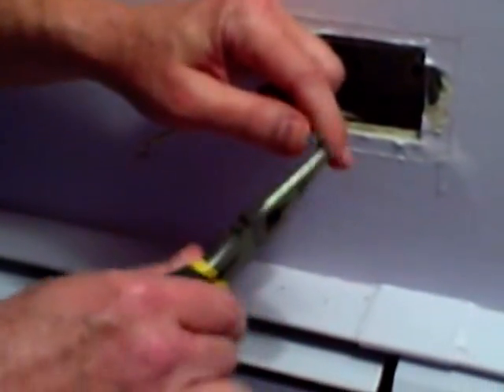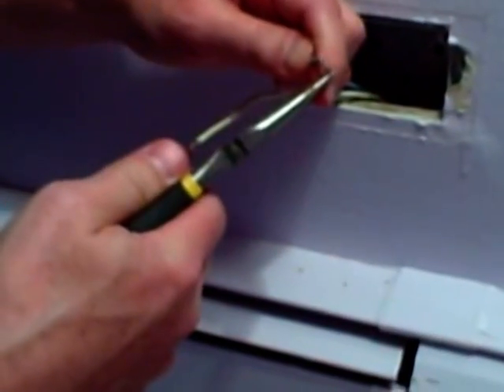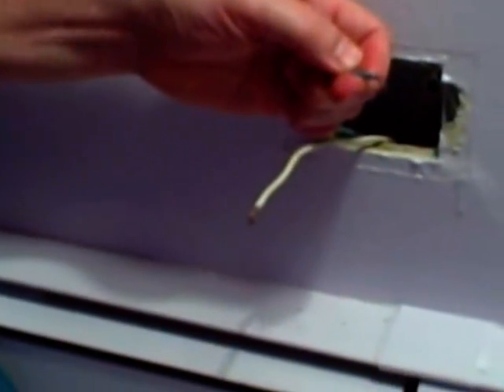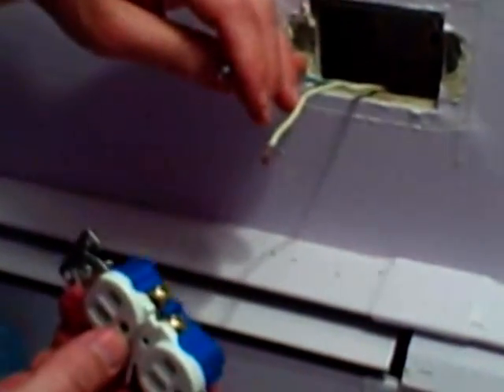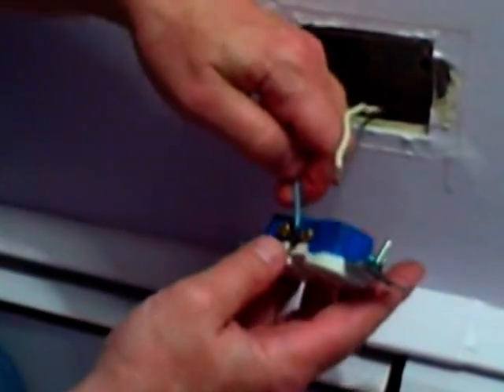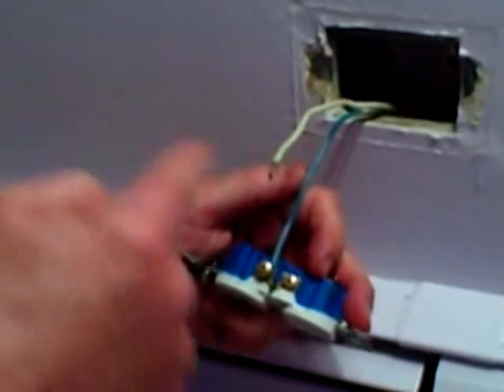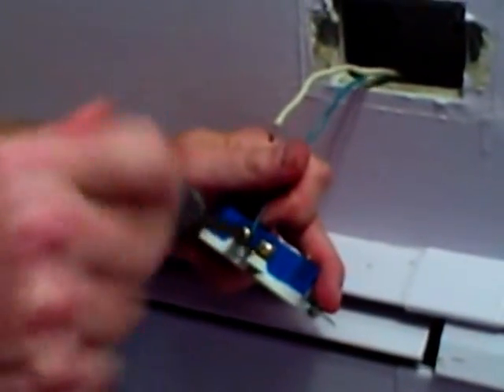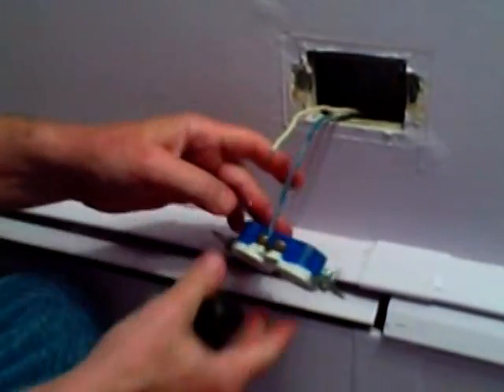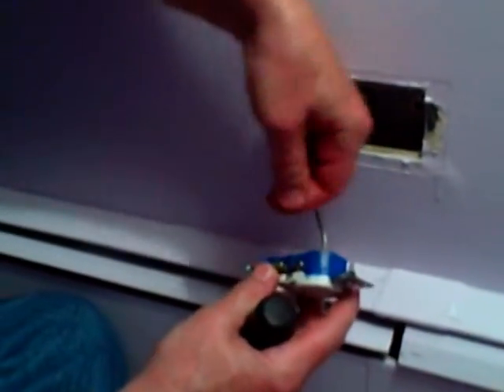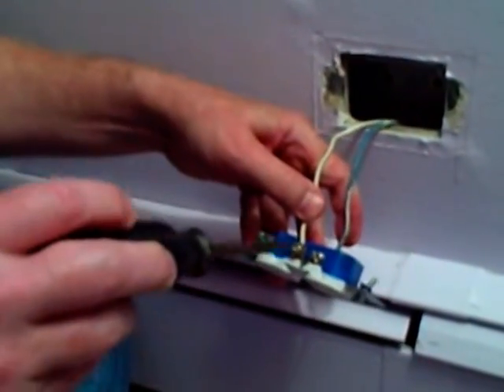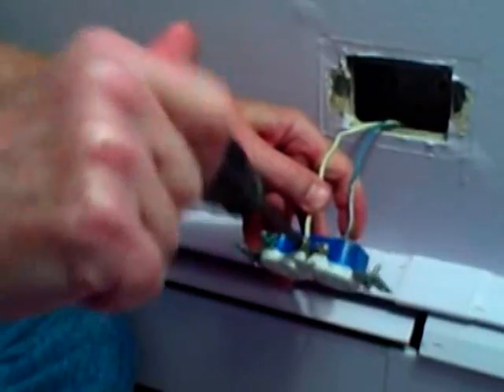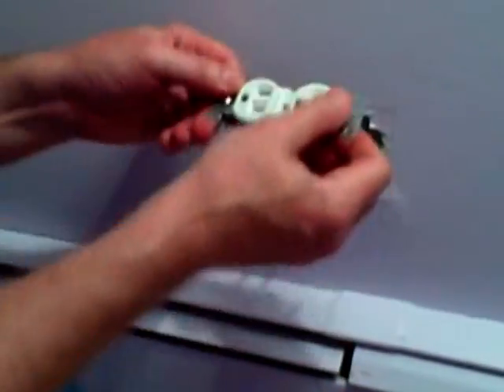With a needle-nose plier, we can just grab the end of the wire and we're going to put a nice loop in this. And it's going to grab around the screw terminal real well. So now we'll grab the new outlet. And what we're going to do is make sure that we take the hot and we're going to wrap it around the brass screw. And we put the hook on clockwise. So as we tighten this screw terminal, it's going to turn itself and tighten around the screw terminal. And then the neutral wire we're going to put onto the silver screw. And we're going to tighten this down clockwise. And that's all there is to it for an end of run.